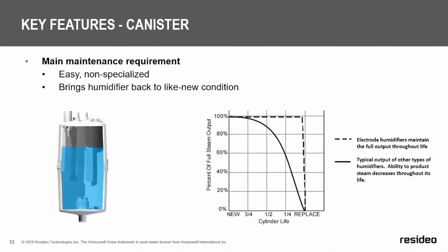The neat thing about the HM750 is it offers full output of steam throughout its entire life. That varies greatly compared to our competition in this electrode steam humidifier category. The dotted line on this chart represents the output of the HM750 from new till replacement date. And the way that works is the patented technology inside our steam humidifier manages the water level in the tank, and that water level starts low, and as those electrodes are consumed throughout their life, the water level will rise. That way, we are always providing new electrode surface to be consumed throughout the life of the humidifier, giving you your full 11 gallons per day output or 22 gallons per day output, depending on power used.